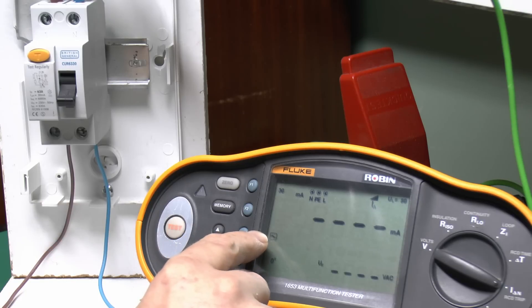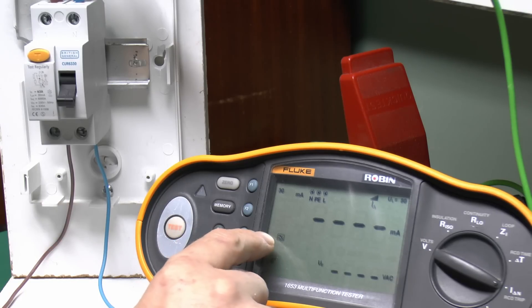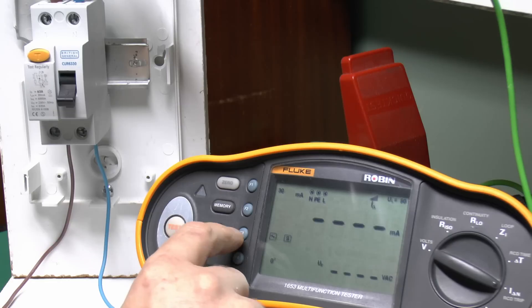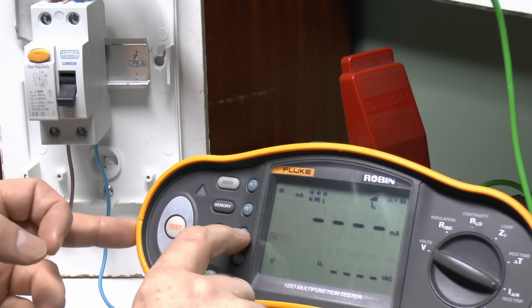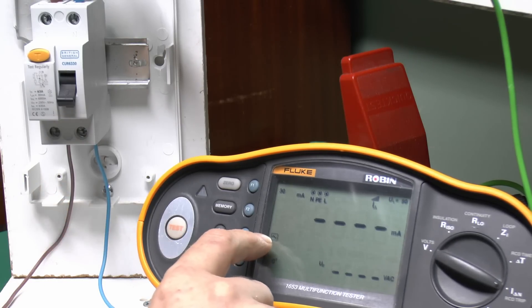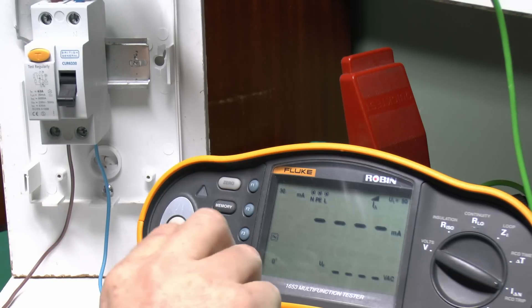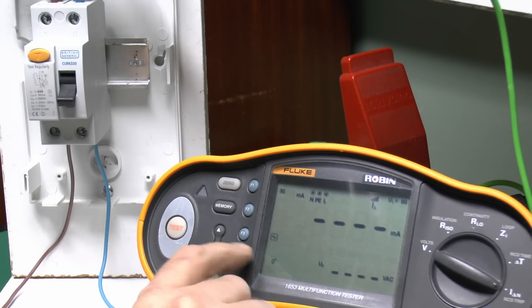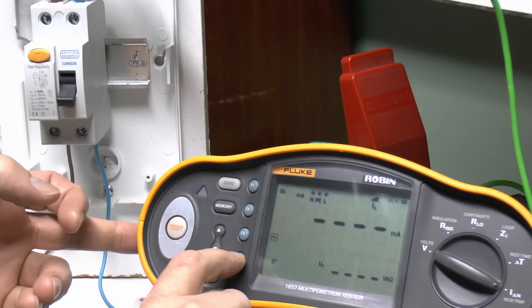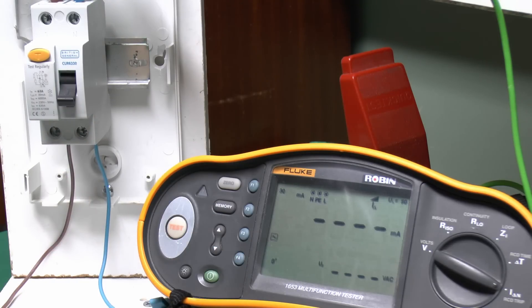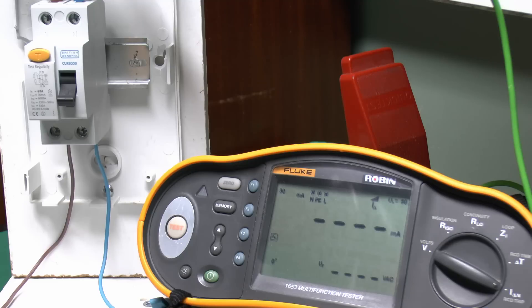And again, we've selected the AC variety there, and there are AC with pulses of DC as well. And you can also do ones with time delay included as well. But in this case, it's just the basic AC variety, so we'll select that. And then the last setting here is either 0 or 180, that refers to the point in the AC waveform at which the testing current is applied, either at the 0 position or 180 degree position, which essentially is either a rising or positive edge, or a falling or negative edge.